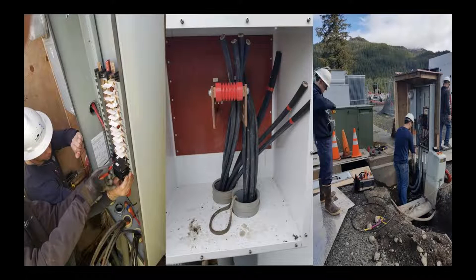This is where I get into the prep on commissioning. Our staff at Cordova Electric are maintenance operators, so they did all the commissioning on our side, landed all the wires, performed all the testing, and went through preventative maintenance training. They're actually the operators who will be running the system. We were very fortunate that there were literally no layers between Cordova Electric and the vendors, so there was no reason not to have our own employees fully involved in the commissioning, since they're the ones operating the system and understand the architecture, the IO, and the mapping.